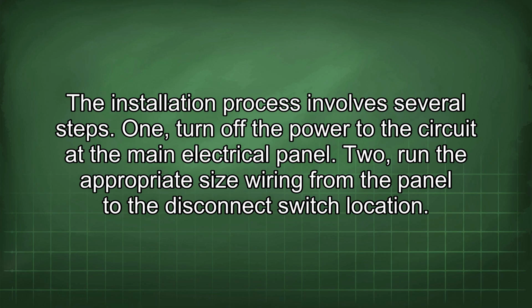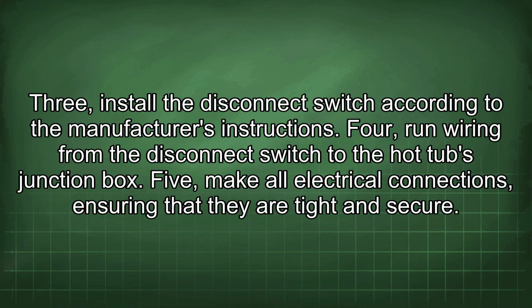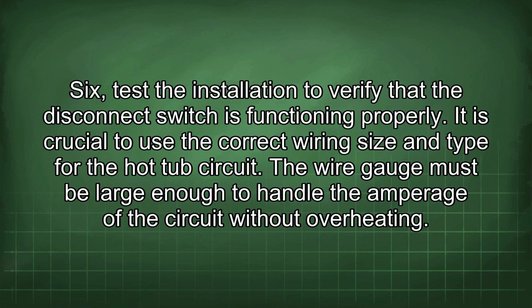The installation process involves several steps. 1. Turn off the power to the circuit at the main electrical panel. 2. Run the appropriate size wiring from the panel to the disconnect switch location. 3. Install the disconnect switch according to the manufacturer's instructions. 4. Run wiring from the disconnect switch to the hot tub's junction box. 5. Make all electrical connections, ensuring that they are tight and secure. 6. Test the installation to verify that the disconnect switch is functioning properly.